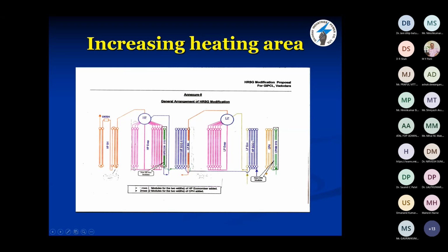Now we studied the drawings and the feasibility of how to increase the heating surface. There was only one possibility: that we could increase the heating surface by providing one HP economizer module. Then we studied the space available in the boiler where we could insert the economizer module. So finally this was the position where we can insert the HP economizer module. My cursor is available, I mean, you can see the cursor.